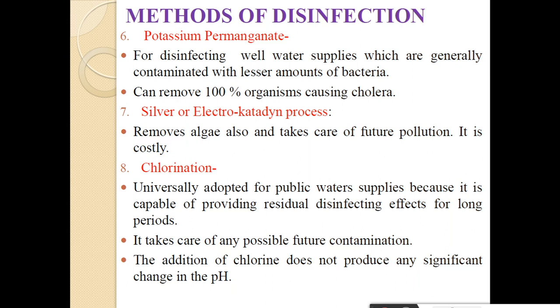Last method is the chlorination method, in which we add chlorine into the water for disinfection purpose. This chlorination method is universally adopted for public water supply because it is capable of providing residual disinfecting effects - that is a very important effect - for a longer period. And it takes care of any possible future contamination of that water. The addition of chlorine does not produce any significant change in pH value. That's why mostly in practice, in water treatment plants, chlorine is used as a disinfectant.